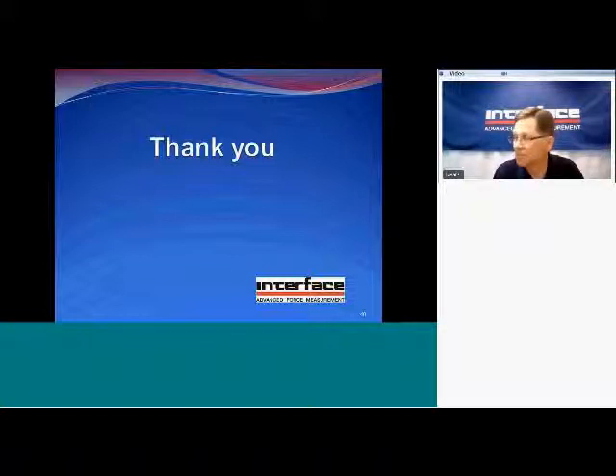Got another one from the field. With the application of the digital processor, the repeatability is more important. Other errors can be corrected with the calibration table. How to achieve the repeatability? How to know the repeatability is lost in real time? I think in the context of this question, what is referred to as repeatability is taken care of in our discussion as what I called non-reproducibility. Non-reproducibility is a broader term than repeatability.